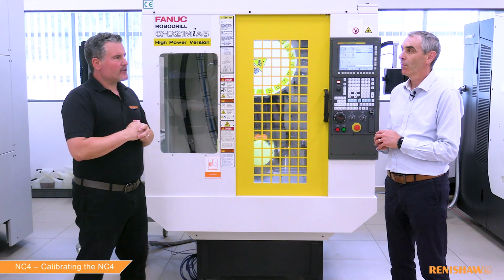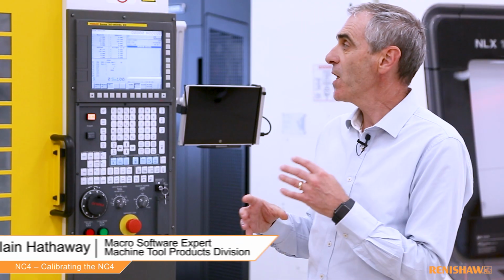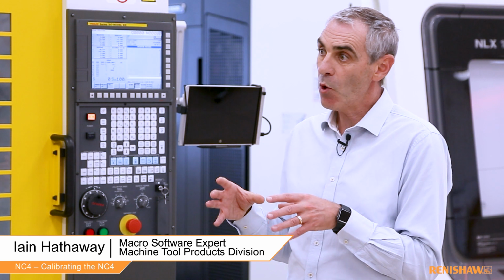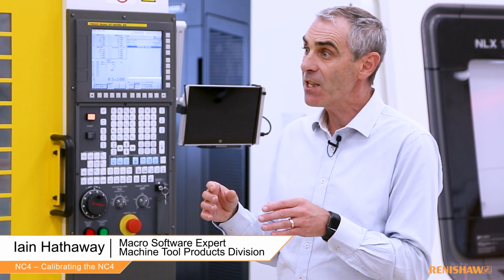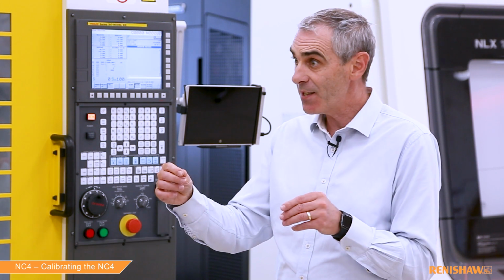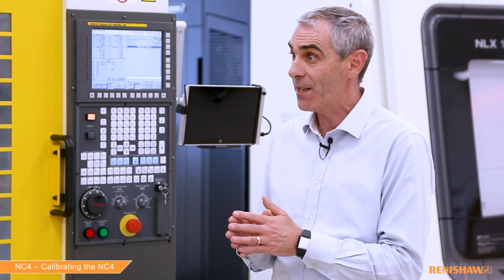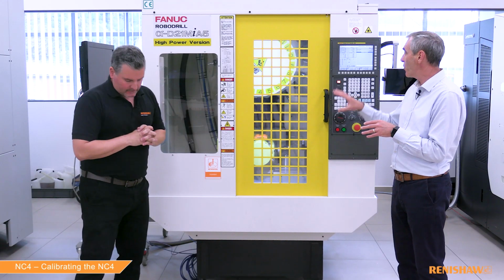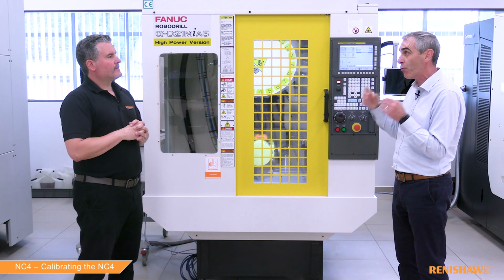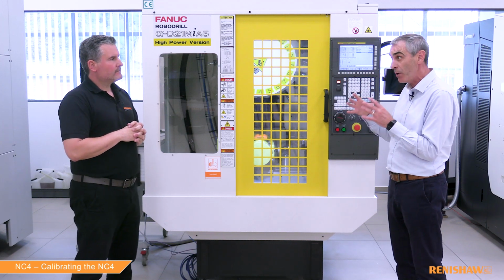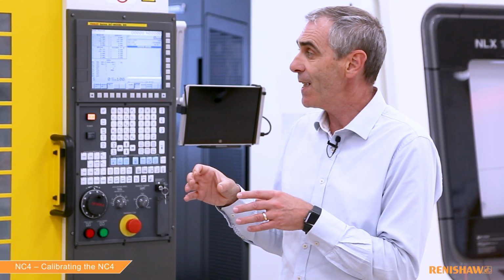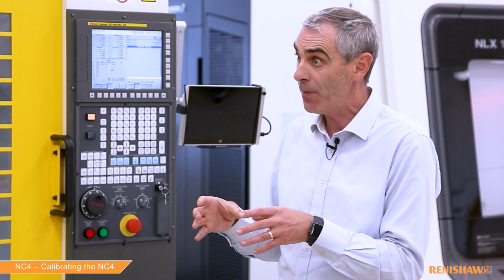Iain, what's calibration? Well, just to summarise, at the end of alignment, what we've done is we've got the laser beam parallel with the Z-axis and parallel with the X or the Y-axis, okay? And we've got stored inside the controller the approximate beam positions, okay? Only the approximate. The whole purpose of calibration is to actually accurately find that beam.